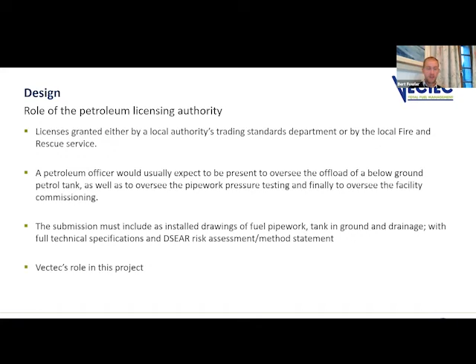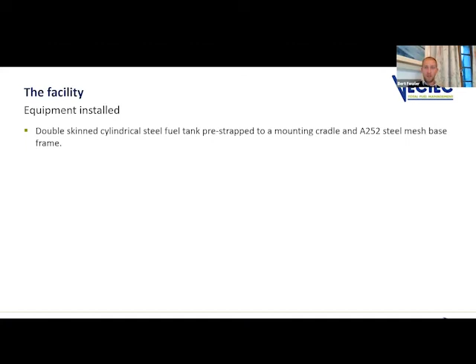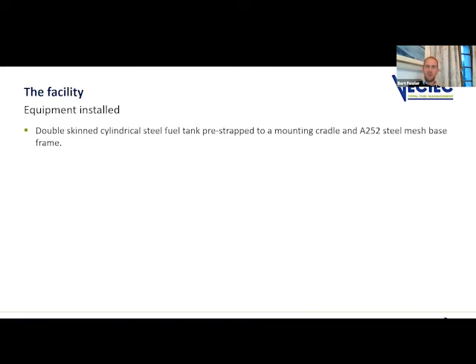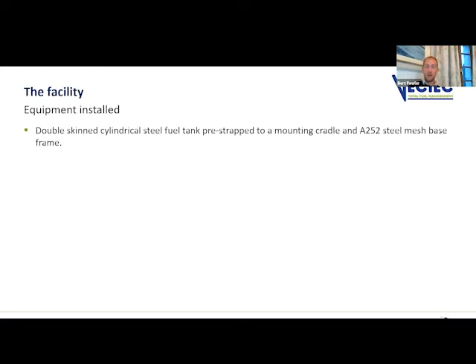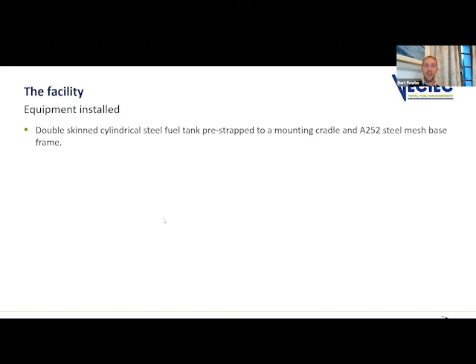The equipment we put in - I won't dwell on this too long - was a double skin cylindrical fuel tank. A process I insist upon on any below-ground install I do is that it arrives pre-strapped to a mounting cradle on a steel mesh base frame. The idea is there's no danger that straps get cast into the wrong location in the excavation - everything's secure, and once that base frame is concreted in, it provides a reinforced concrete base. There's also no requirement for operatives or engineers to go down into the excavation, which is a big HSE concern, particularly in the construction industry.